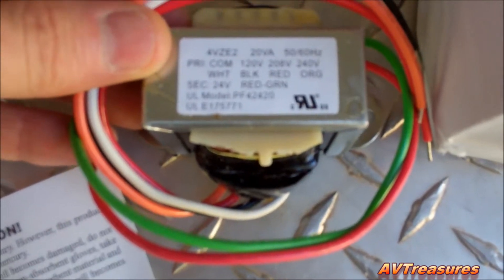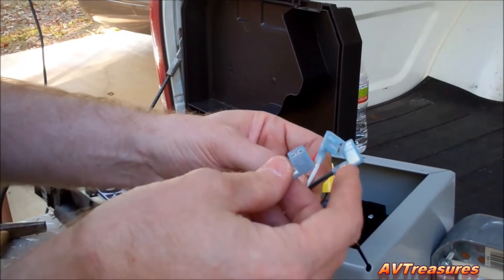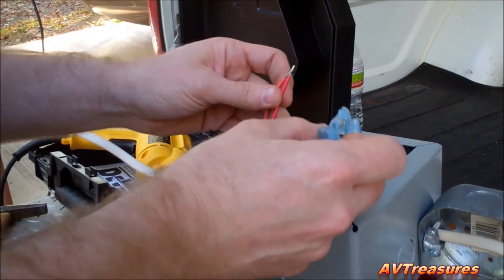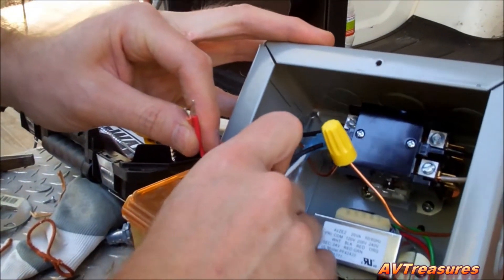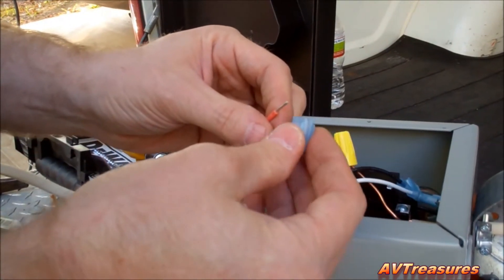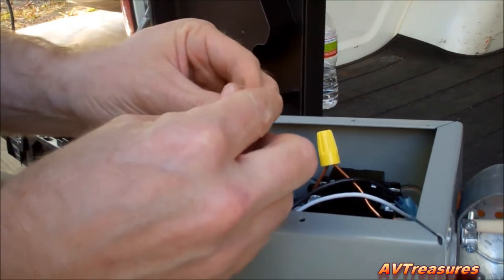I just got a little 20VA flip-mount transformer here — it's a Dayton. That'll be plenty for that contactor. I'm using some quarter-inch 90-degree terminals on my low voltage. This is the high voltage going to the transformer. I'm going to connect it on the line side of the contactor, and then I'll break my thermostat wire in between — that's where I'll turn it on and off.